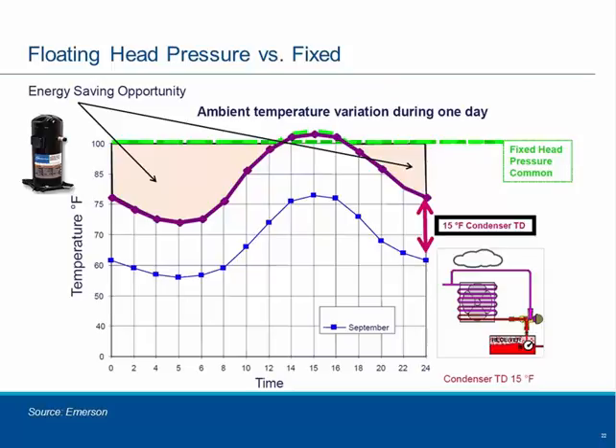And let me set this up for you. The chart shows the ambient temperature variation during one day in September in Ohio, I think was used as the example here. The ambient temperature is that dotted blue line. Many outdoor condensing units are set up or designed so that the head pressure, the condensing pressure, is fixed. And that's that dotted green line at the top. 100 degrees Fahrenheit saturated condensing is very typical. So that even when the ambient temperature drops very low, the head pressure is set up there very high. What we're advocating, as a major energy saving measure, is looking at floating that head pressure down, taking advantage of lower ambient temperature fluctuations.